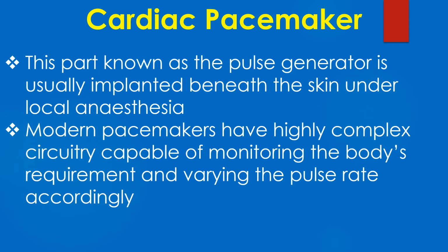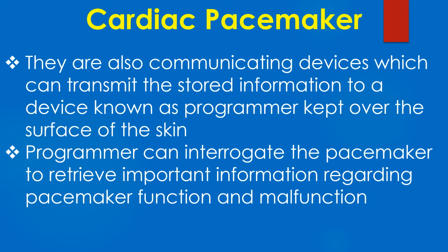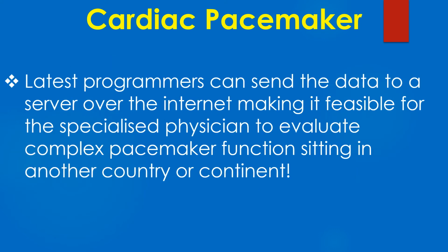Modern pacemakers have highly complex circuitry capable of monitoring the body's requirement and varying the pulse rate accordingly. They are also communicating devices which can transmit the stored information to a device known as a programmer kept over the surface of the skin. Programmer can interrogate the pacemaker to retrieve important information regarding pacemaker function and malfunction. Latest programmers can send the data to a server over the internet, making it feasible for the specialized physician to evaluate complex pacemaker function sitting in another country or continent.